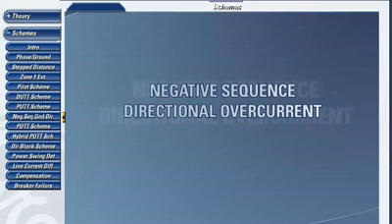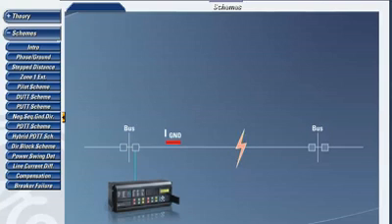When a fault occurs on a transmission line, somewhere on the line, currents are flowing to ground. Measuring the direction of the flow of the ground current is used to assist some of the pilot-aided distance protection schemes in determining if the fault and the source of the ground current are located on their transmission lines.